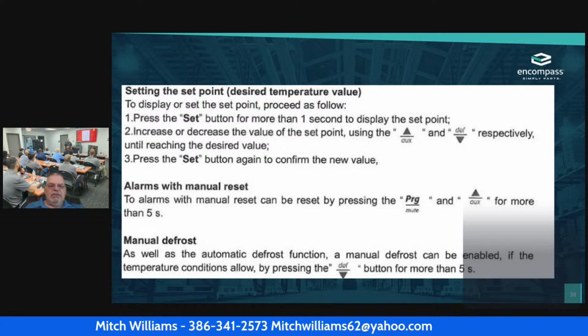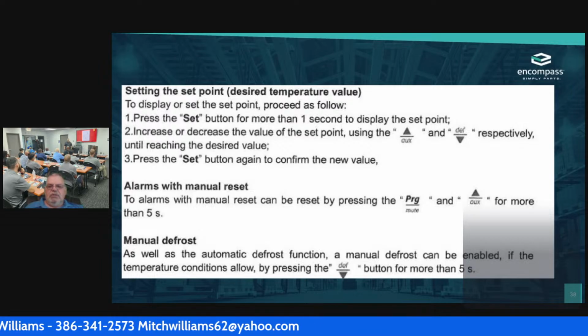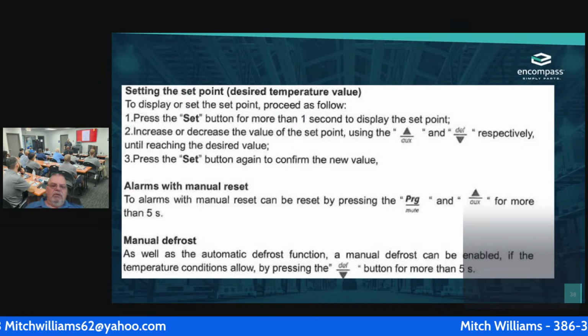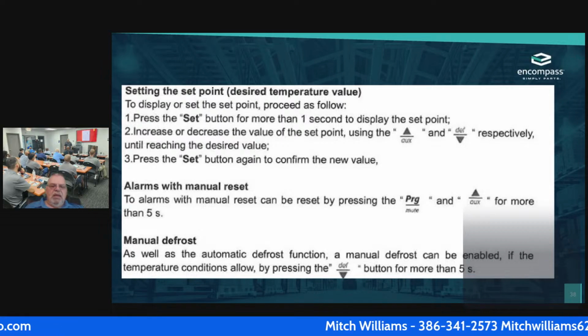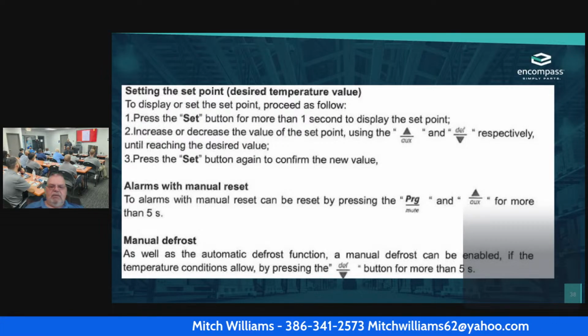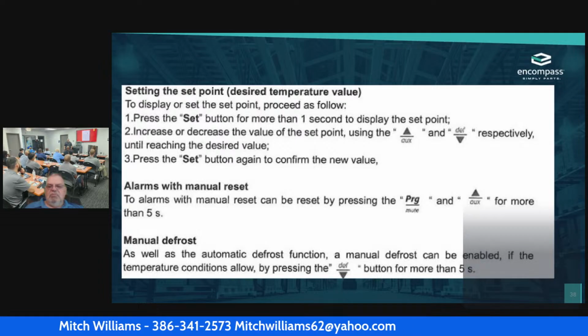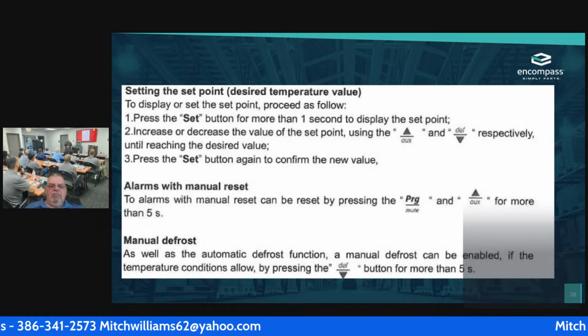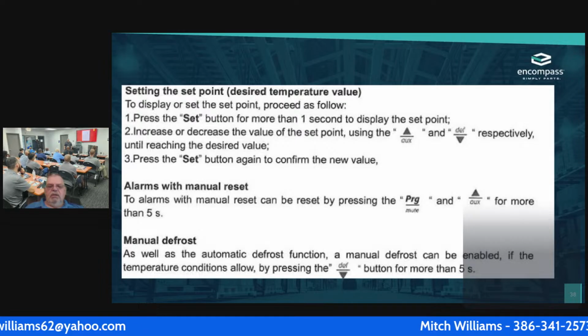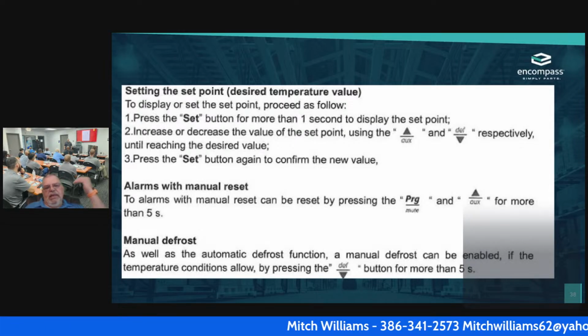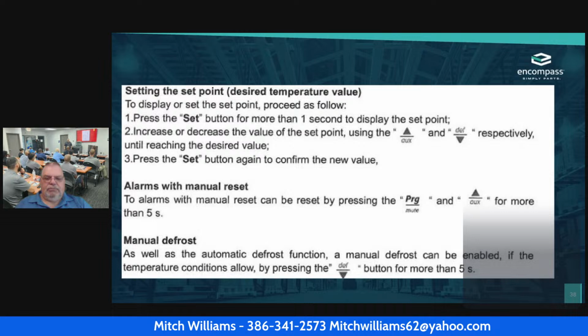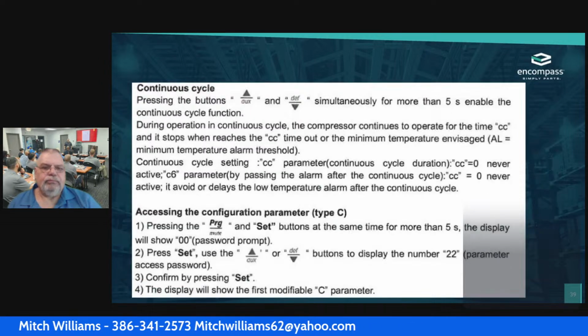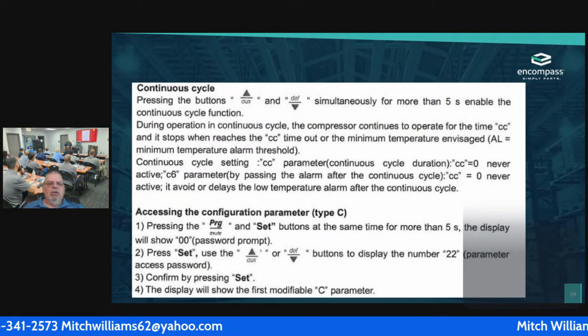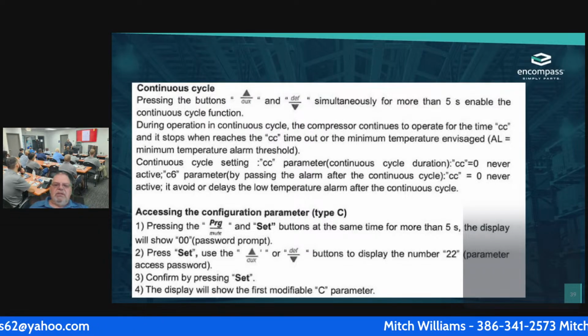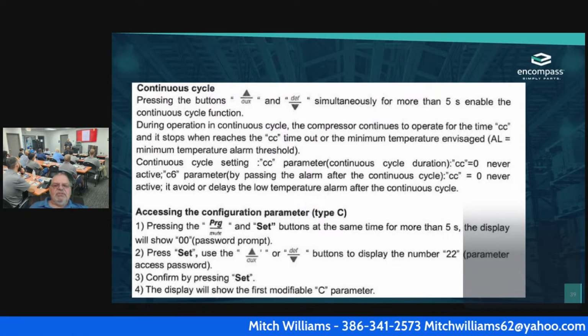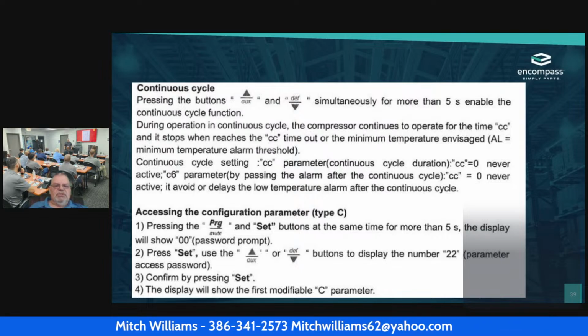Alarms with a manual reset: I can press the program and the up button for more than 5 seconds. If I want to do a manual defrost as well as the automatic function, a manual defrost can be enabled, if the temperature conditions allow, by pressing the down button for more than 5 seconds. And that automatically puts me into a defrost. My continuous cycle: by pressing the up button and the down button simultaneously for more than 5 seconds, that enables the continuous cycle function.